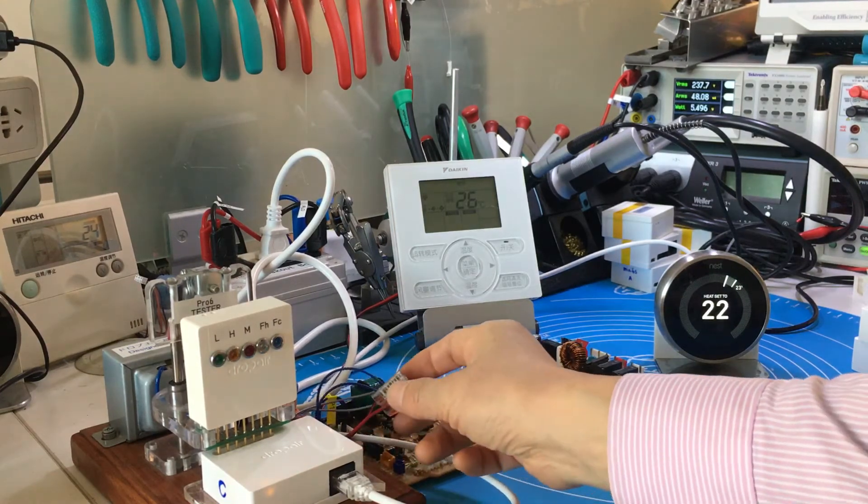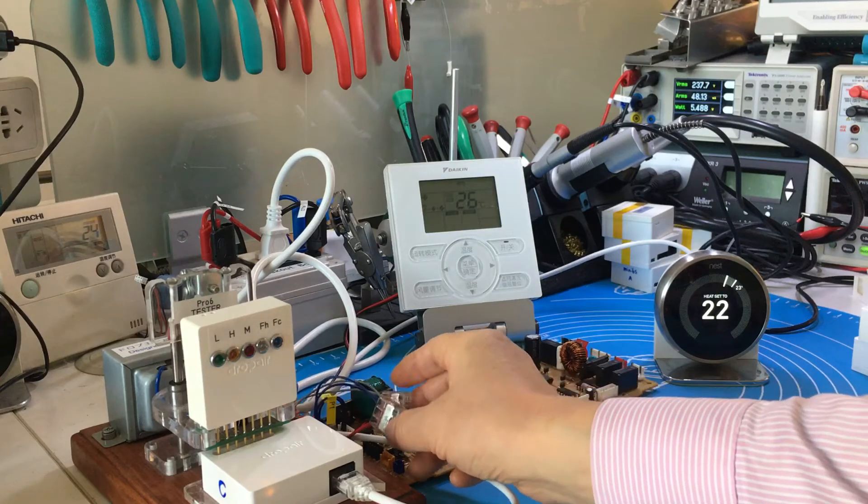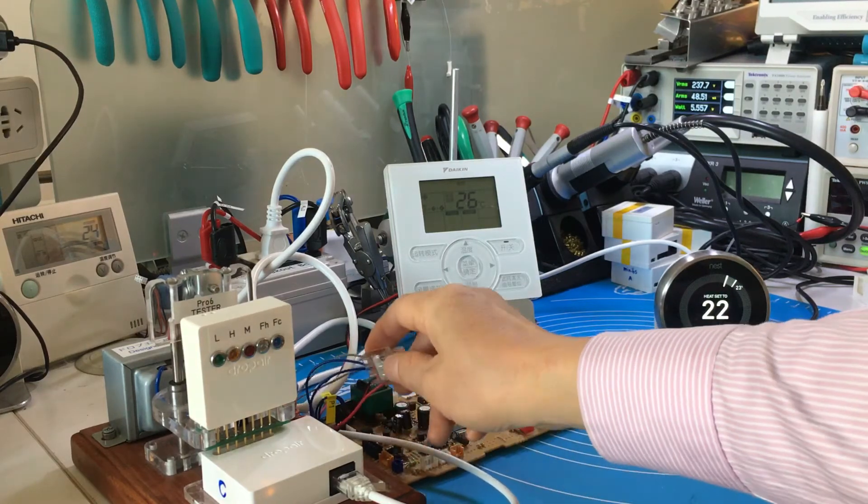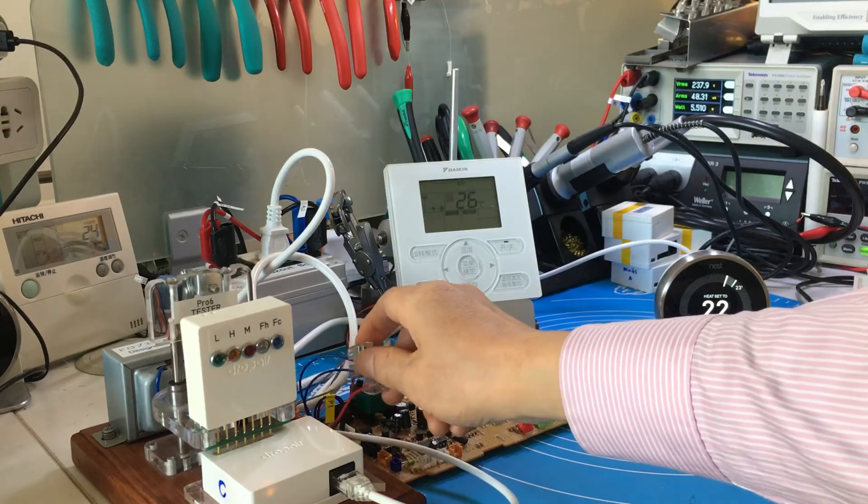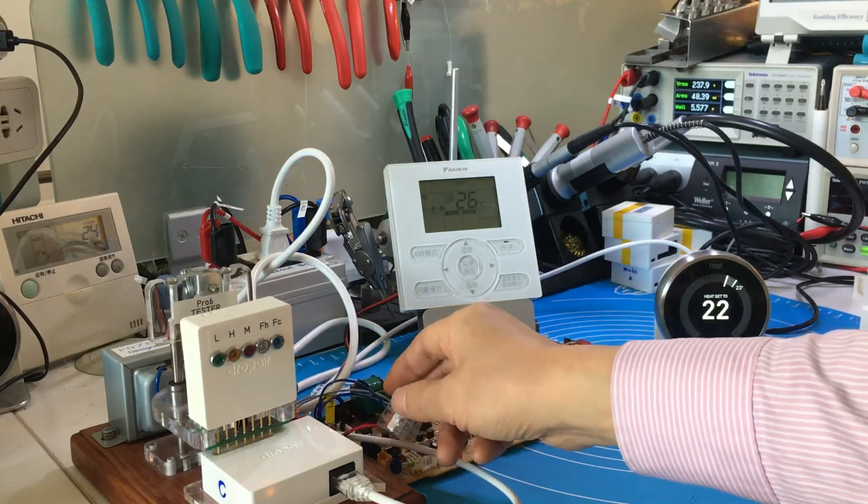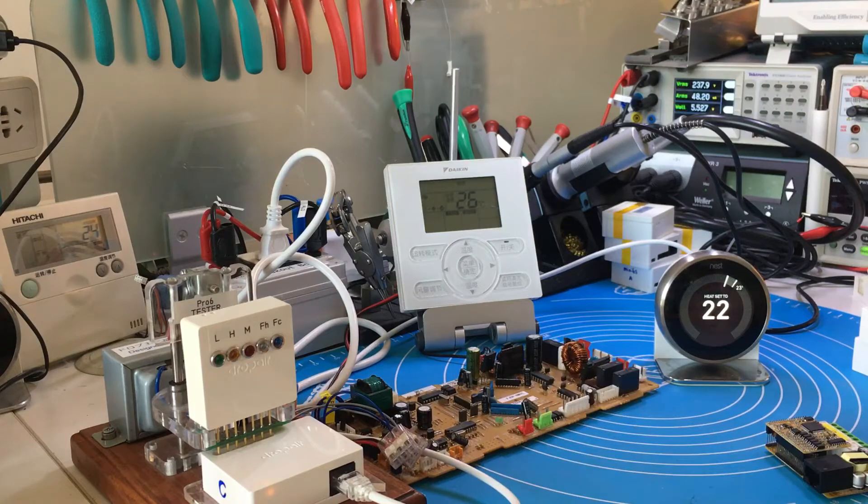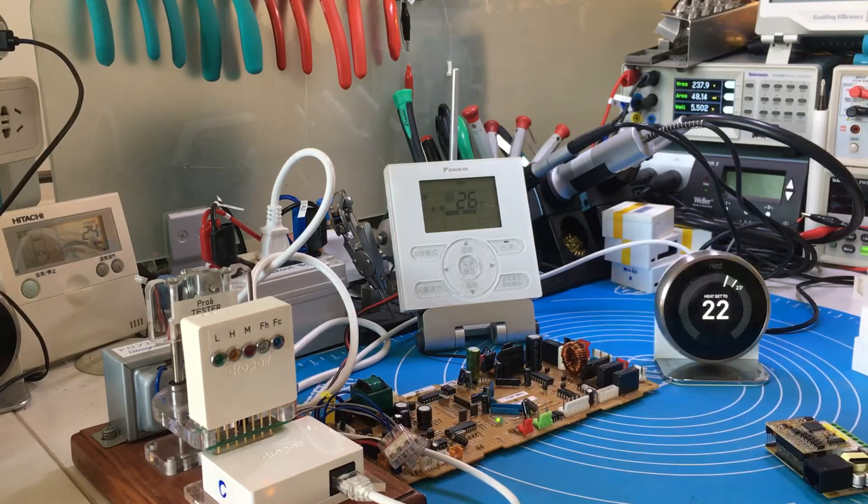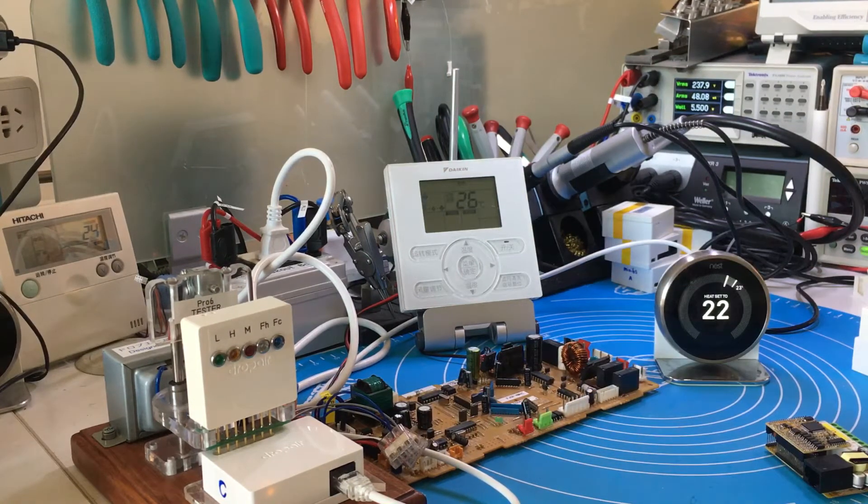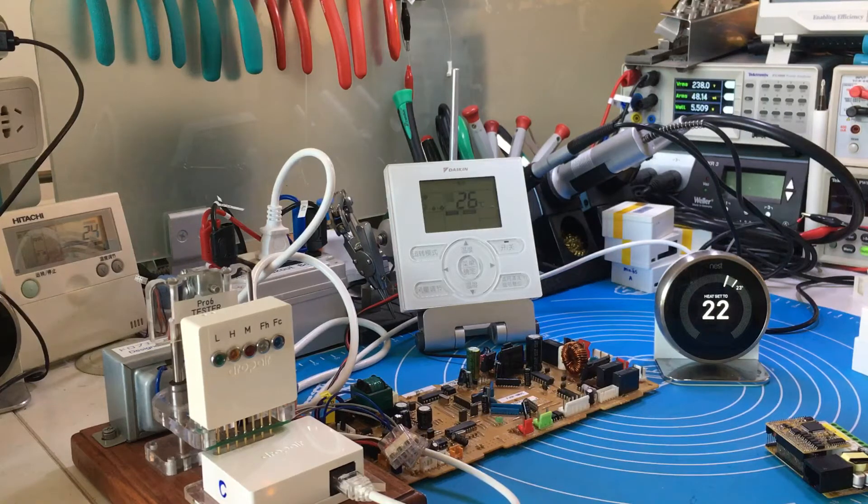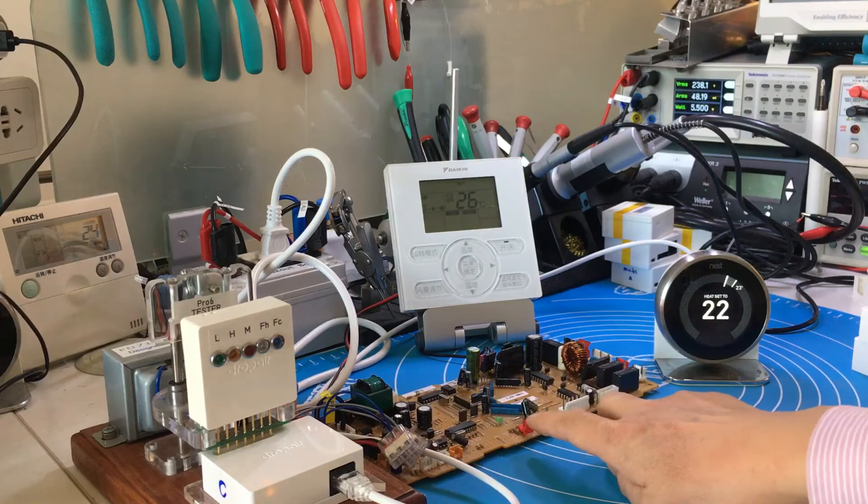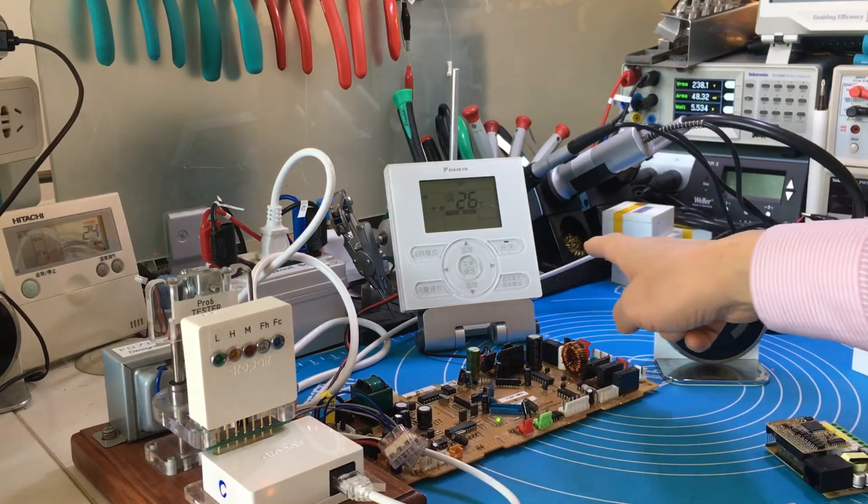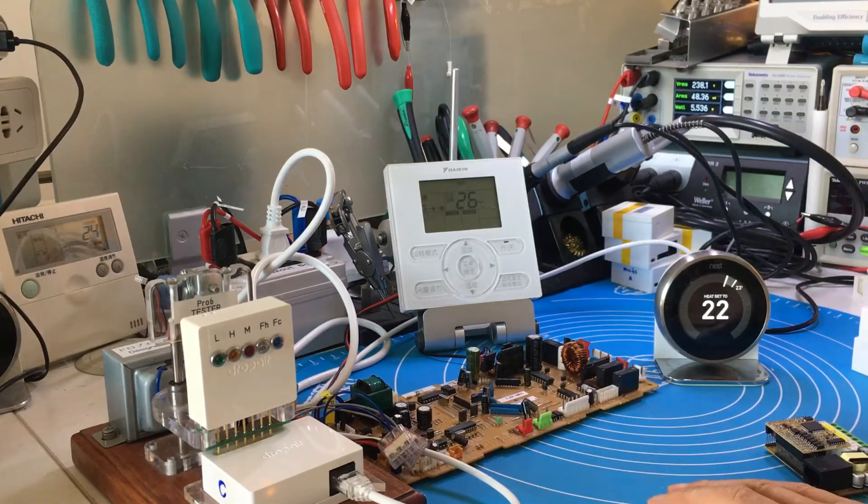The adapter connects with the Daikin system using the P1 and P2 communication cable line. This cable connects with the indoor unit and the original thermostat together. This is the Daikin indoor unit, this is the original thermostat which now acts as a monitor, and this is the Nest thermostat.